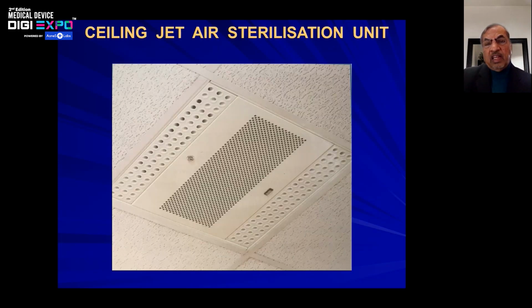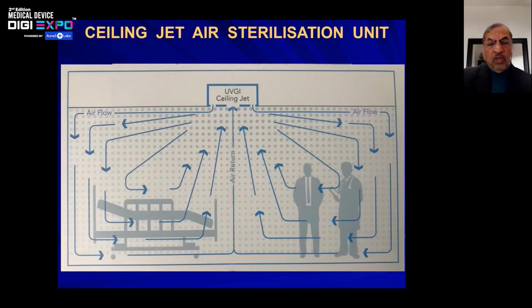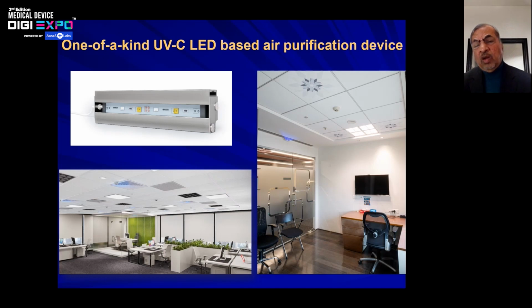The ceiling jet air sterilization unit is another form which uses UV, where a UVGI ceiling jet is embedded in your false ceiling and the airflow is taken care of and disinfected. Now, a lot of people came up with this: after COVID, the guideline issued was that the return air also be ducted. So it becomes difficult for existing hospitals to carry out such modification. So this UVC LED-based air purification device is fixed in the diffuser. You could see here in one of the pictures where it is fixed in the diffusers so that it will automatically clean the air, and the blue color you are seeing is an LED, it is harmless.